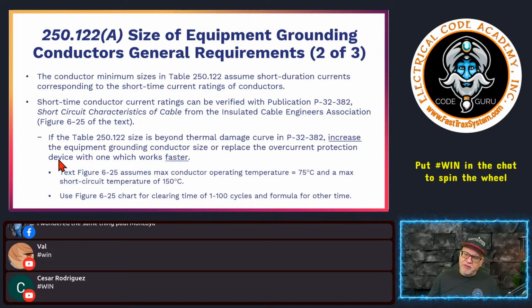It says if the table 250.122 size is beyond thermal damage curves in this document, increasing the equipment grounding conductor size or replacing the overcurrent protective device with one which works faster can be a scheme that your engineer may try to accomplish. This is on the engineer. This is not something that you as an electrician need to tackle. You don't need to get this document from ICEA. Don't need to try to do any of that.